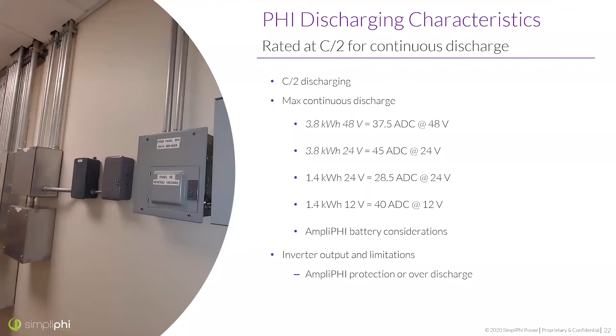Inverters, when you're using our standard batteries, do not have the ability to limit the discharge oftentimes. Most inverters don't. So keep in mind that we would require sizing to make sure that you do not over discharge. So the battery should be twice the inverter's continuous output. So if you've got an 8 kilowatt inverter, you should have 16 kilowatt hours of batteries minimum. If you want to know more about that sizing and requirements, check out my BAT 101 or go onto our website and check out our sizing calculators that go over this really well. But again, the AmpliPHI will actually make sure that it programs the inverter not to do this, so you don't really have to worry about sizing so much.